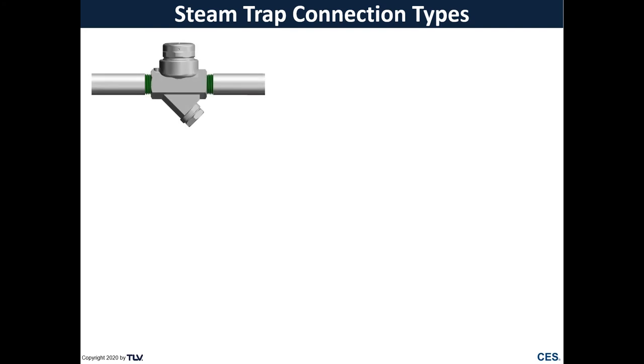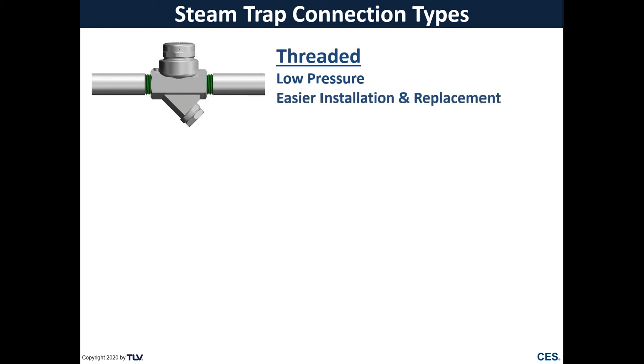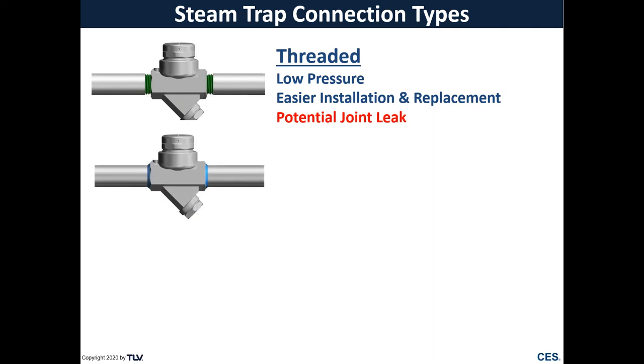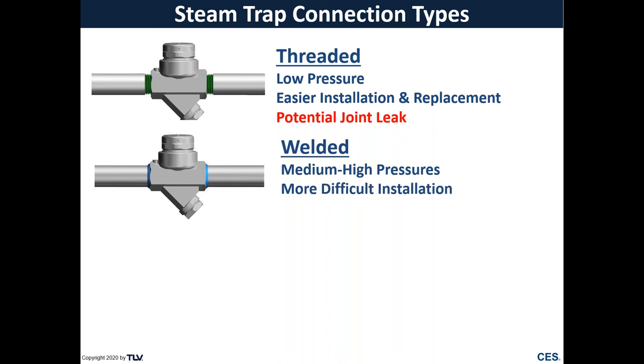Now we'll take a look at different types of connections for steam traps. And this is pretty common throughout all types of valves and fittings. The first is a threaded connection. This is generally seen on low pressure applications, and it's easy to install and fairly easy for replacement. But the downside is that it is also a potential leak joint, versus something like a welded trap, such as a socket weld or butt weld trap, which is typically used on medium to higher pressures, but it is more difficult to install because it involves welding. And it also is more difficult and takes longer to replace because it requires cutting and rewelding a steam trap in that line.